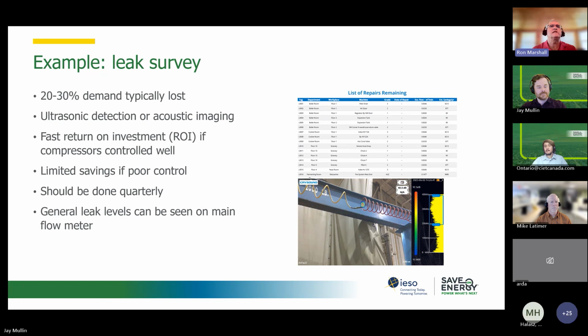So typically 20 to 30% of a plant's air on average is lost due to leaks. So if you have an ultrasonic gun or acoustical imaging device, you can very quickly find where the leakage is, even in a noisy plant, right? Those detectors block out the ambient noise, and you can just hear leaks. Not only compressed air, but steam leaks, vacuum leaks, gas leaks. Maybe you're using argon or oxygen or other gases, nitrogen. They're much more costly than compressed air, so it's a side benefit in doing a compressed air leakage study. You can find those gases as well.